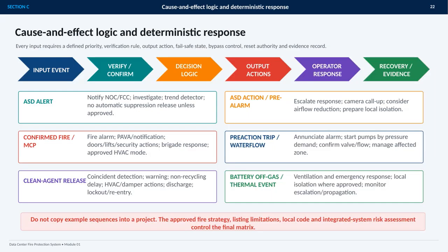This section focuses on cause and effect logic and on making every response deterministic rather than improvised. For each input, we need to define the priority, the verification or confirmation rule, the required outputs, the fail-safe state, bypass controls, reset authority, and the evidence that will be recorded. The essential principle is that every event must lead to a controlled, documented response. The sequence moves from the input event through verification and decision logic to output actions, operator response, and recovery evidence.